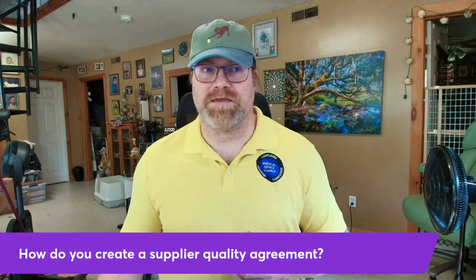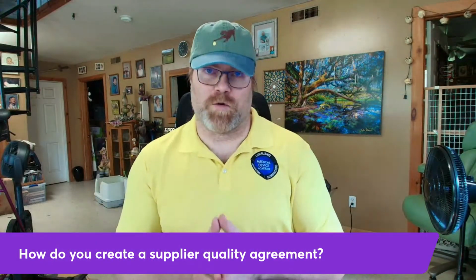What the supplier quality agreement is supposed to cover from a regulatory standpoint is who is responsible for what quality system requirements and regulatory requirements that are in the ISO 13485 standard and in the applicable country regulations. So if you're selling it in the US, the FDA regulations. Who's responsible for what? And guess what? There are going to be a few things that are shared that you just can't do all by yourself. You just can't. So we're going to walk you through how to document that. And so the real question here that we're trying to cover is, how do you create a supplier quality agreement?